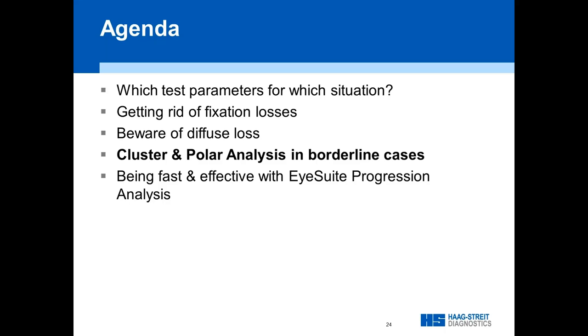Regarding the fixation control level, medium is recommended — that's also the default in the latest software version. Previously the default was automated eye tracking on the Octopus 900 where the chin rest repositions you, but there was feedback that patients are distracted by this. So now we start with medium and see how it goes.